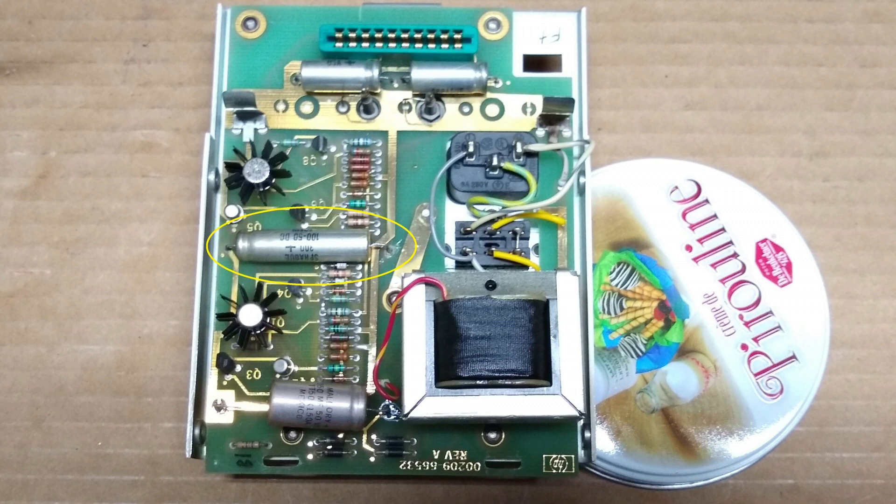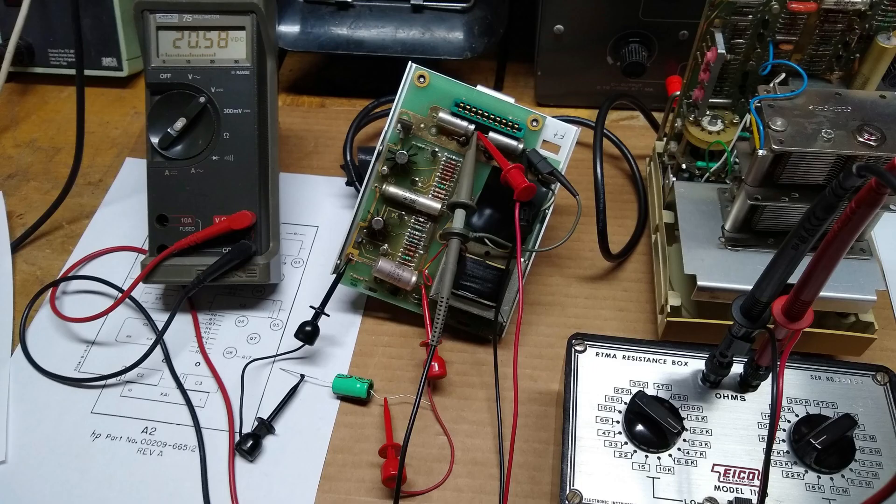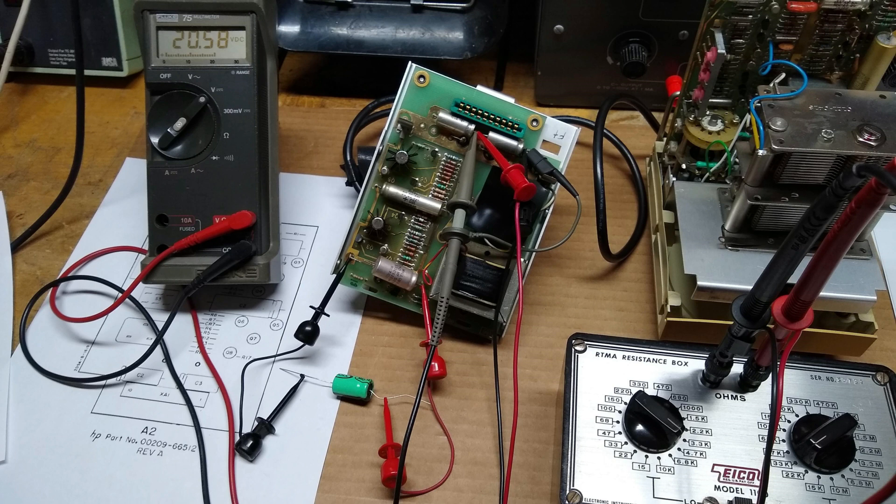I then connected the power supply to AC mains and did a little troubleshooting to discover that the Mallory capacitor no longer was acting as a smoothing filter. Logically, I proceeded by disconnecting one side of this capacitor from the circuit board and temporarily connecting an external capacitor in its place. The power supply positive rail was then properly regulated and measured 20.58 volts DC.